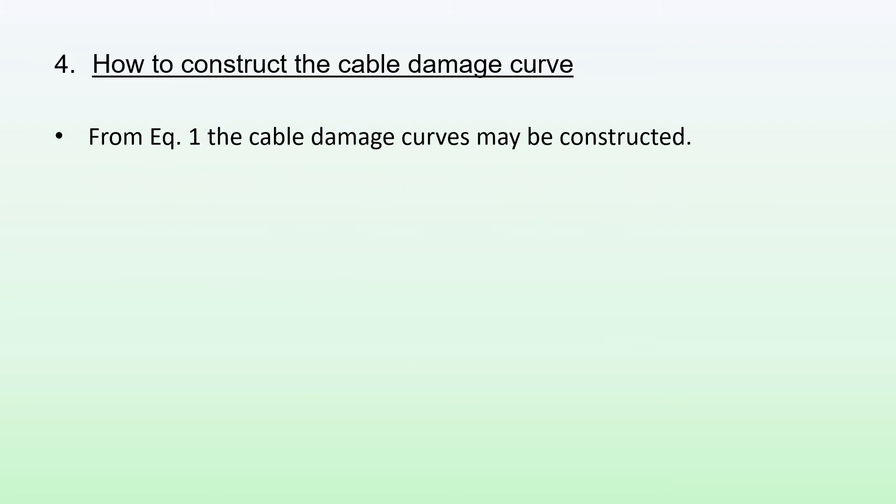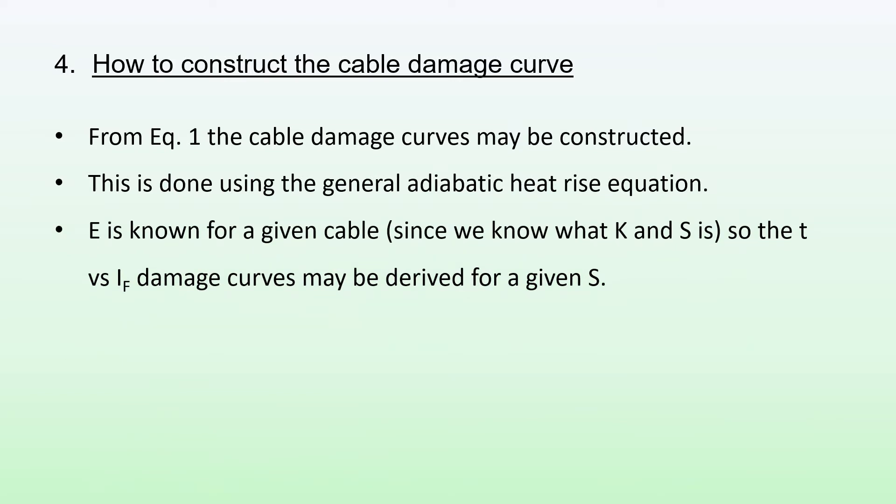How to construct the cable damage curve? From equation 1, the cable damage curves may be constructed using the general adiabatic heat rise equation. E is known for a given cable because we know what K and S are, so the t versus If damage curves may be derived for a given S. We can rearrange equation 1 to make t the subject of the formula, so we get t equals K squared times S squared divided by If squared.